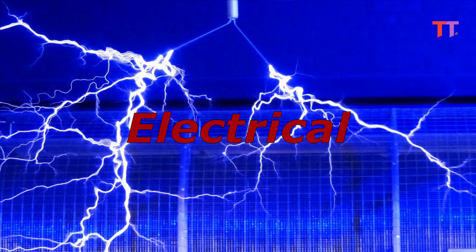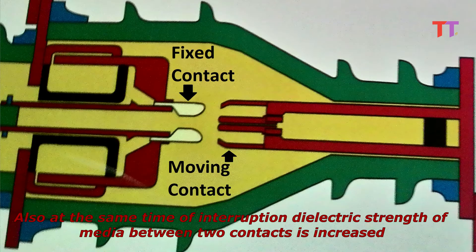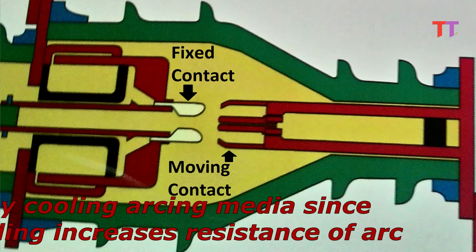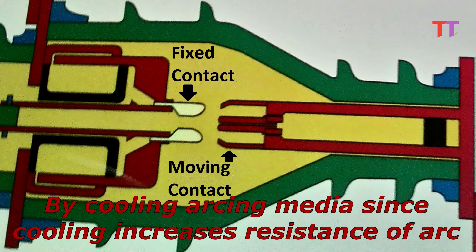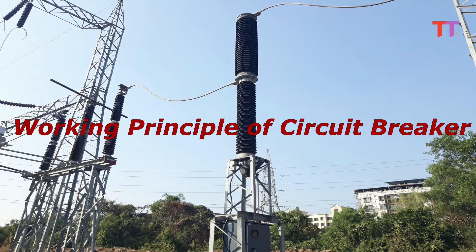Now the electrical aspect of the working principle. Since the purpose of a circuit breaker is to minimize arc formation, current interruption is done at the time the current crosses zero during its cycle. Also at the same time, the dielectric strength of the media between the two contacts is increased. This is done by compressing the ionized arc, since compression accelerates de-ionization, by cooling the arcing media — as cooling increases resistance of the arc — or by replacing ionized arcing media with fresh gases.